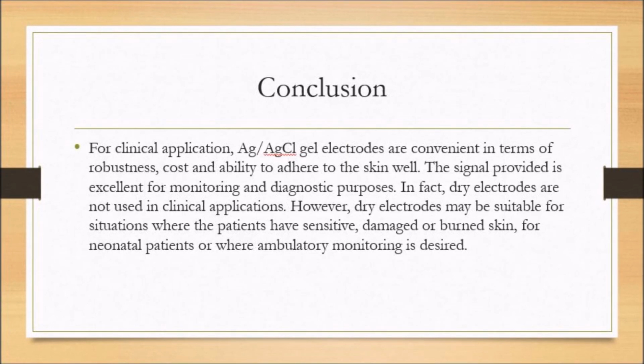And lastly, for the conclusion, for clinical applications, silver chloride gel electrodes are convenient in terms of robustness, cost, and ability to adhere to the skin well. The signal provided is excellent for monitoring and diagnostic purposes. In fact, dry electrodes are not used in clinical applications. However, dry electrodes may be suitable for situations where the patients have sensitive, damaged, or burned skin, for neonatal patients, or where ambulatory monitoring is desired.